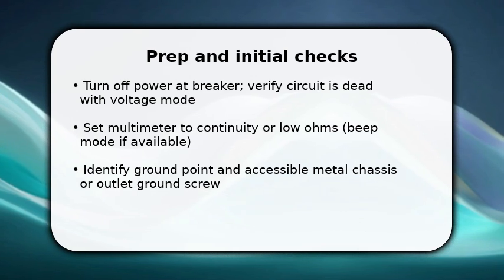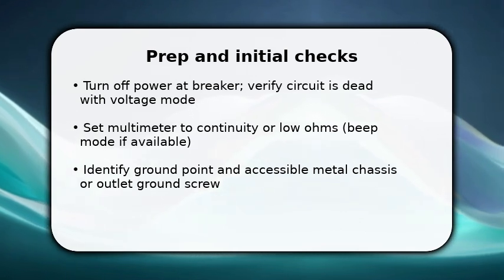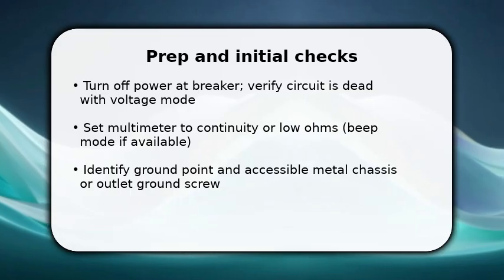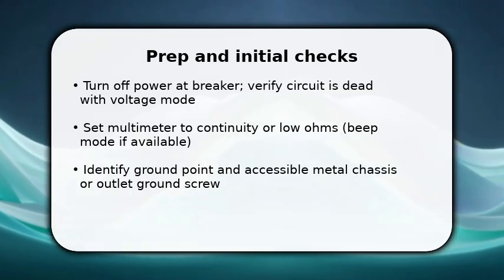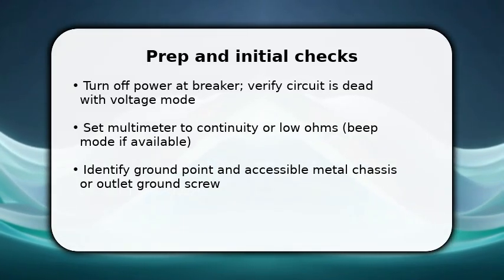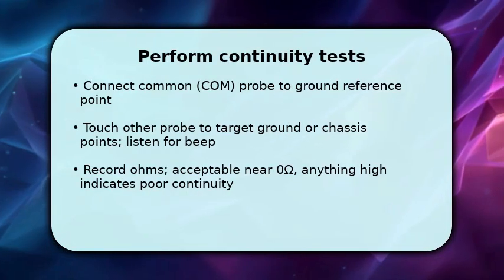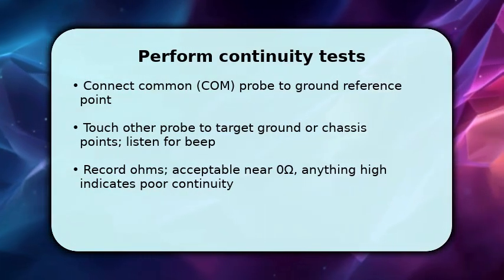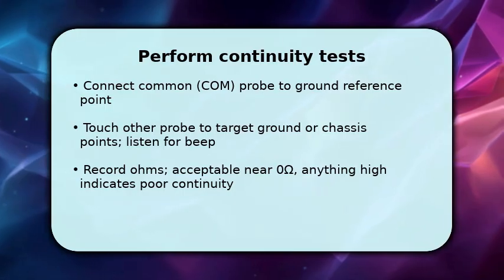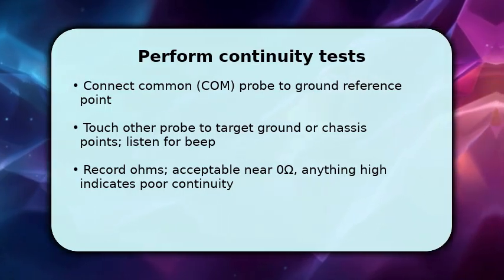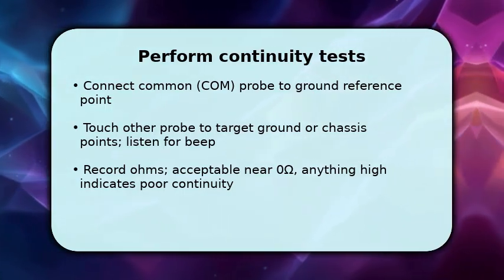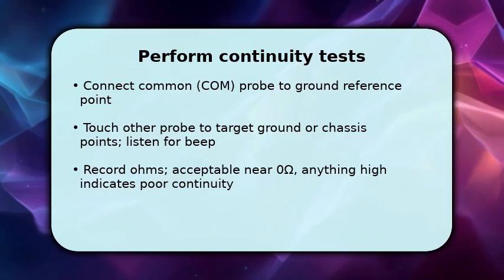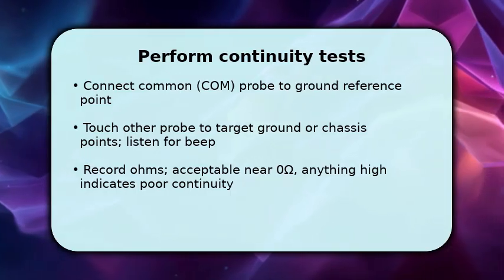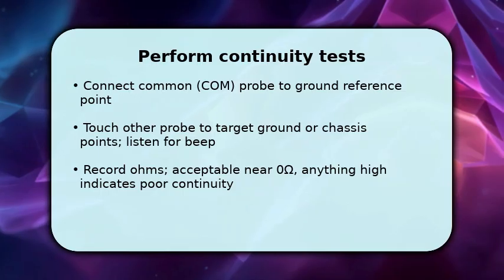Make sure your probes and hands are steady and insulated. Start by clipping or touching the COM probe to your verified ground reference. This creates the return path for the meter. Then touch the positive probe to each target ground location, the outlet ground, chassis, or conduit, and listen for the beep or watch the low ohm reading. If you see near 0 ohms, the continuity is solid. Small fractions of an ohm are fine.